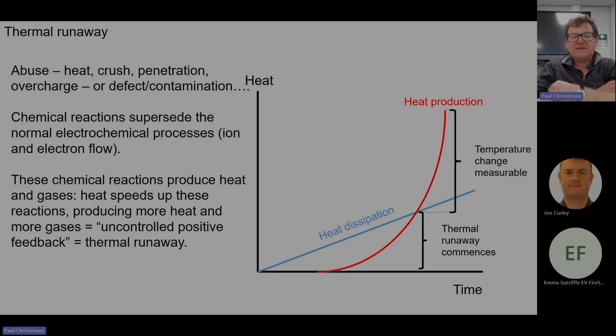Heat is produced exponentially, the red line. It's dissipated linearly, the blue line. But it's only dissipated from the surfaces of the battery, whereas it's produced throughout the whole volume of the battery. Hence, the bigger the battery, the more heat is retained. When those lines cross, there's a measurable temperature rise, and that's the simplest definition of thermal runaway, or uncontrolled positive feedback: one degree centigrade per minute up to ten degrees centigrade per second. A better definition is when those exothermic processes become self-sustaining and cannot be stopped. That's thermal runaway.